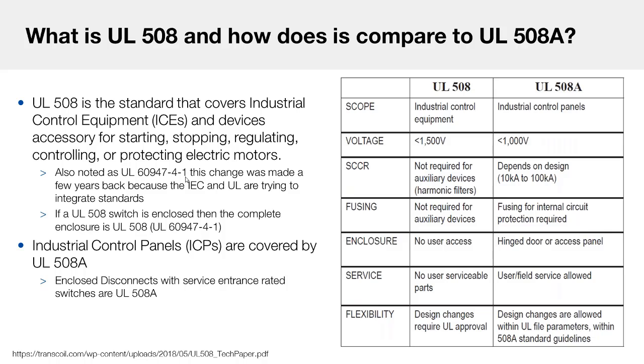standard. It's just that the UL and the IEC are trying to integrate their standards, so that's why you may see both of these. But if you have an enclosed UL508 switch, the standard of the complete solution is still UL508 or UL 60947-4-1, depending on when, again, the enclosed solution was certified. So for example, in our later slides, you will see the Socomec enclosed disconnect switches, and those are rated UL 60947-4-1 because we added those to our product range after the integration of the UL and the IEC standard.